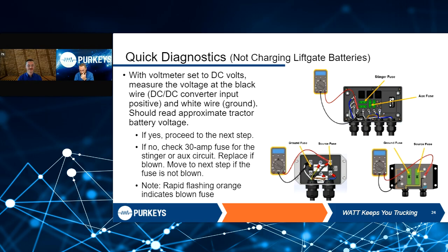I get asked the question a lot: why do we fuse the ground circuit? The reason is, if those pump motors aren't properly grounded, the current is going to find a path somewhere, and typically that's through our 50 foot of harness. So versus burning up 50 foot of harness, we'll blow a fuse for you. So if it is flashing rapid orange or amber, don't just replace the fuse. Really dig in and look at the pump motors, make sure they're properly grounded, and make sure your batteries are grounded to the frame of the trailer, and that will likely fix that problem.